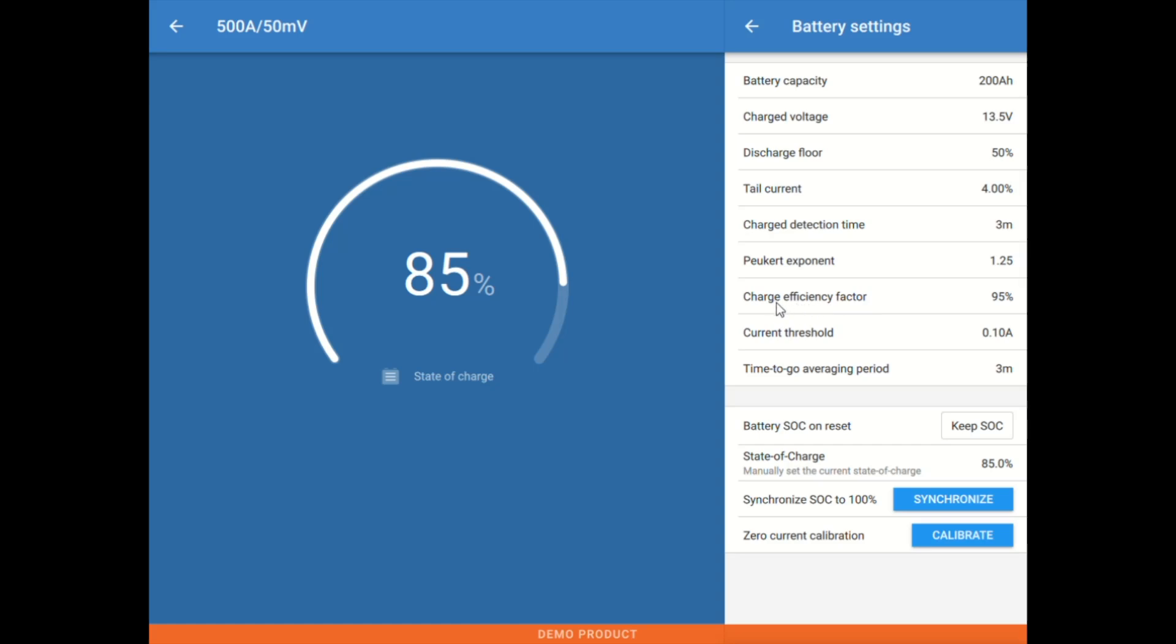This is the charge efficiency factor, 95% is typical for lead, maybe 96% for higher efficiency, and then we'll go 98%, 99% for most lithium.